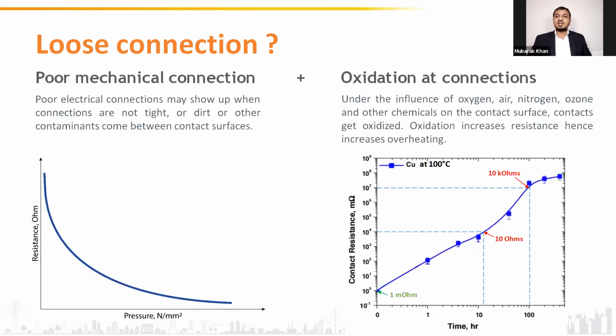Now, what is a loose connection? Loose connection is the common term used by the majority of people in the industry. But the way I would like to present it better is an improper connection or insufficient connection. Loose connection can be because of poor mechanical connection. A poor mechanical connection means connections are not physically tight. It is not tightened properly. Or dirt or other contaminations are coming between the contact surfaces.